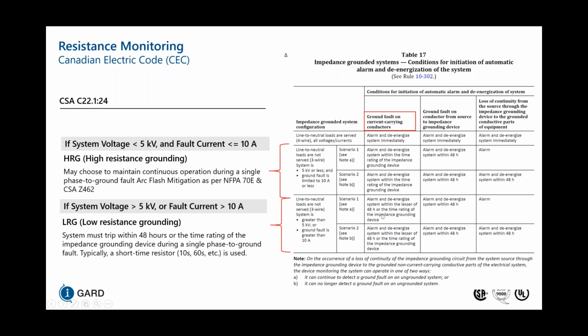Now, for systems that are greater than 5 kV or when ground fault is greater than 10 amps, it indicates for ground fault that we alarm and de-energize the system within the lesser of 48 hours or the time rating of the impedance grounding device. But typically for these higher voltages and current levels, you're going to be dealing with more wattage back at the source when a ground fault occurs. So typically consultants like to use 10-second or 60-second rated resistors and trip on first fault with respect to the coordination of the rest of their relays in their feeders and subfeeds. That allows the ground fault to be basically isolated to the area where the fault is coming from.